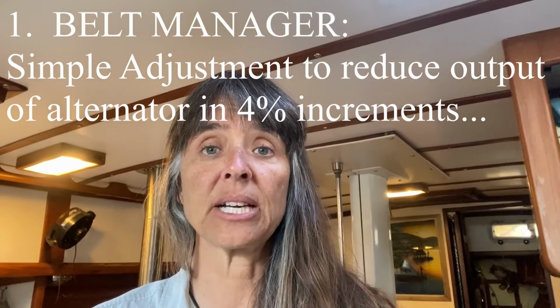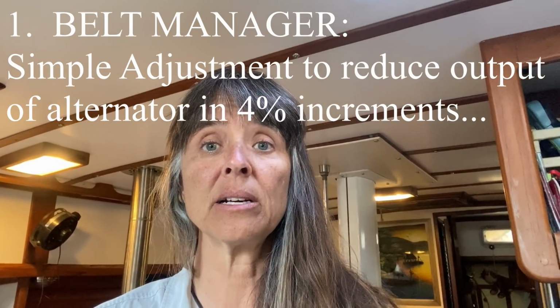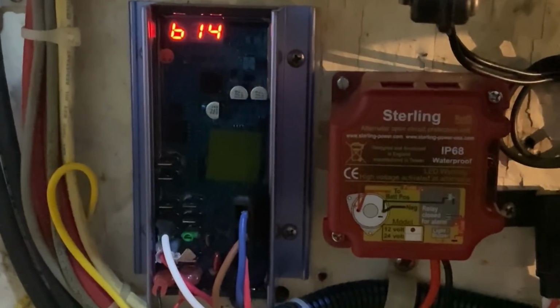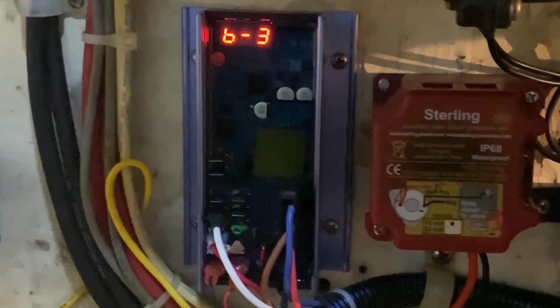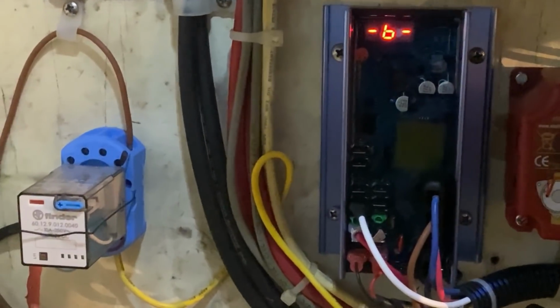Belt Manager is a piece of electronics and software within the Balmar Max Charge 614 regulator that lets me dial down the maximum amount the alternator is allowed to put out. So if it can put out 170 like ours can, maybe I tell it to only put out 160 or 150. That way I'm not pressing it to an absolute maximum, because lithium batteries will take the maximum the alternator can shove at them—that's why alternators that worked fine with lead acid batteries don't work so fine with lithium. We use the Belt Manager to reduce how much our higher output alternator can put out, just to protect it.